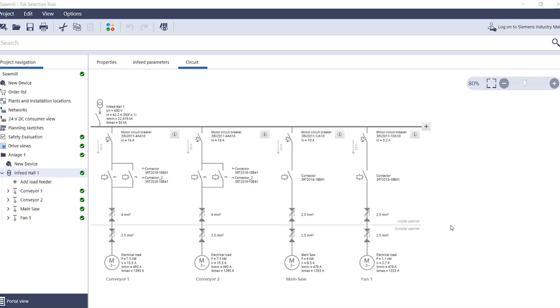This is a calculation that is ultimately required in the new EN 60204-1 standard of 2019 and serves to ensure that the switchgear used can detect and switch off the maximum short circuit current and also the minimum short circuit current.